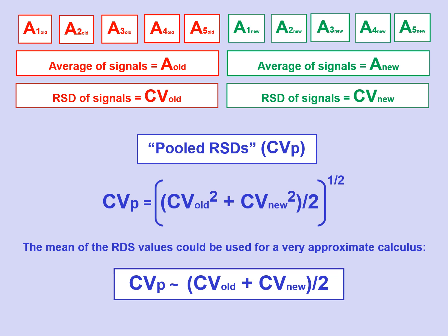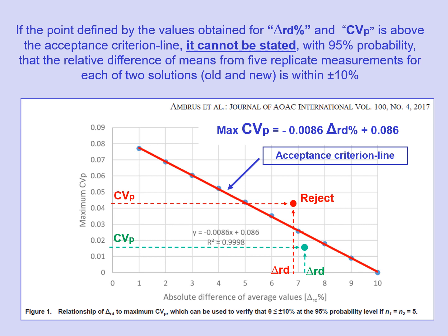Finally, it is sufficient to check whether the weighted coefficient of variation obtained — CVp — is greater or less than the maximum value max CVp defined by the linear equation established by Ambrus et al., for a value of the relative difference of the means equal to that obtained, ΔRD in percentage. In other words, if the point defined by the values obtained for ΔRD and CVp is above the acceptance line established by Ambrus et al., it cannot be affirmed with 95% confidence that the relative difference in the means of the responses obtained from five injections of both standards — the old and the new — is within ±10%.